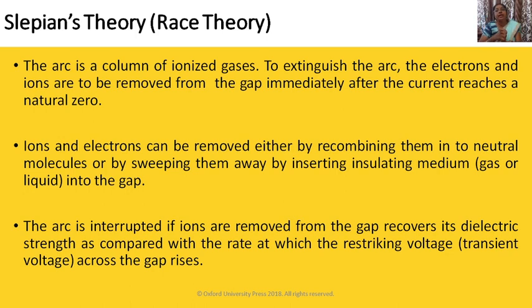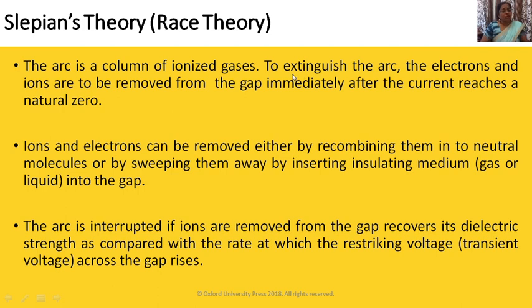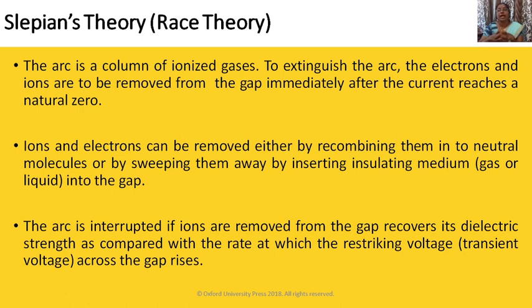In the race theory, there is a race between dielectric strength recovery and the rate of rise of restriking voltage. The arc is a column of ionized gases. To extinguish the arc, the electrons and ions are to be removed from the gap immediately after the current reaches a natural zero. Ions and electrons can be removed either by recombining them into neutral molecules or by sweeping them away by inserting an insulating medium — gas or liquid — into the gap. By inserting that medium, we make the medium between the two contacts deionized, so the restriking voltage is less and dielectric strength is more, and the arc is interrupted.